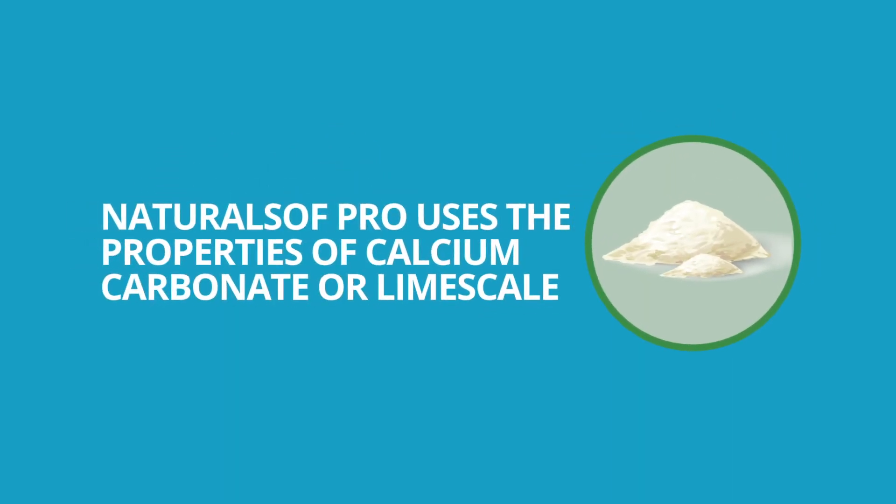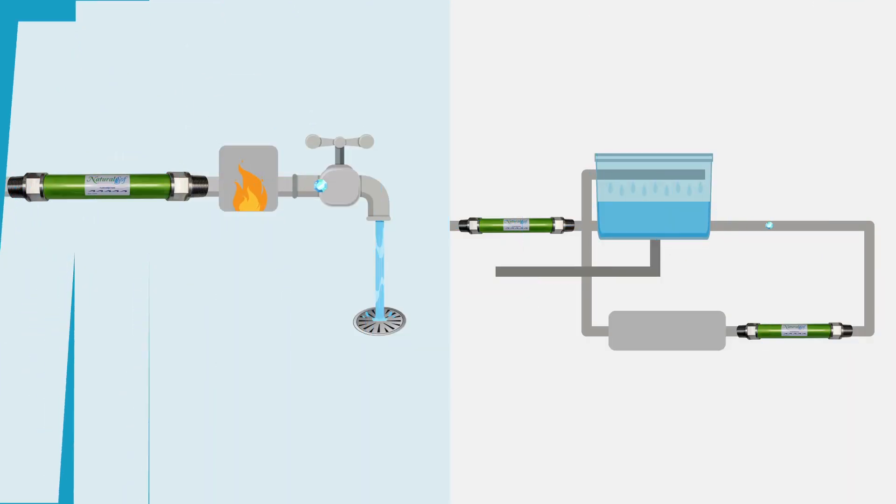NaturalSof Pro will either keep your equipment completely lime scale free or dramatically reduce downtime associated with descaling. NaturalSof Pro uses the properties of calcium carbonate, or lime scale, to create a soft, non-bonding lime scale crystal less than 1 micron in size. The crystals flow in a drain in single-pass applications and are removed through blowdown in recirculating applications like cooling towers.